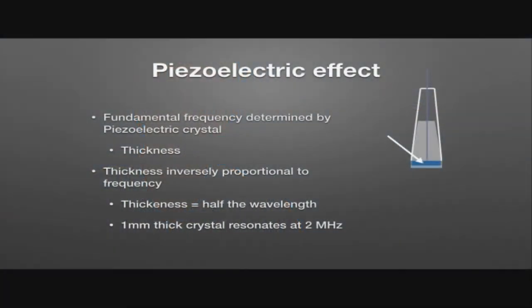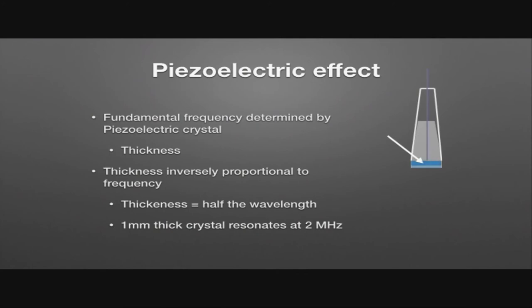The frequency produced by these piezoelectric crystals is related to the thickness of the crystal layer. Thickness is inversely proportional to frequency, so a thicker crystal gives a lower frequency. Crystal thickness is typically half the wavelength — for example, a 1 mm thick crystal resonates at 2 MHz, while a 2 mm thick crystal would have a greater wavelength and therefore a lower frequency.